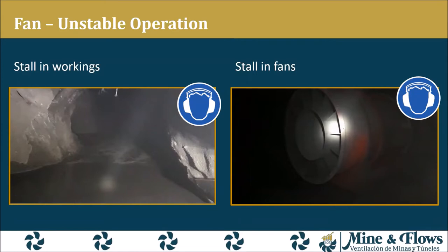In the video on the left, we will listen to the characteristic sound of a fan operating in a stall region. This sound is like the blowing of an old train and must be an alarm of a potential premature failure of the equipment. Be careful with the noise, please.